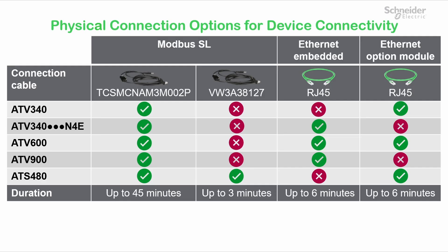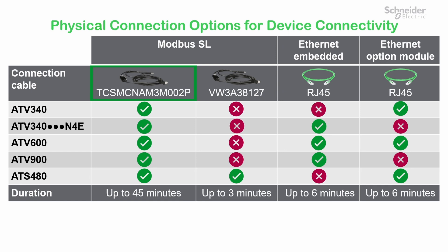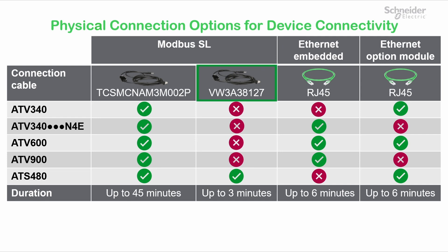You have multiple options to physically connect your device, depending on the Altivar product you are using. This table shows all these options. You can connect your computer to your device's Modbus port using TCSM-CNAM3M002P or VW3A38127 cable, or connect your computer's embedded Ethernet port to your device with an Ethernet cable, or connect your computer to your device's Ethernet option module with an Ethernet cable.